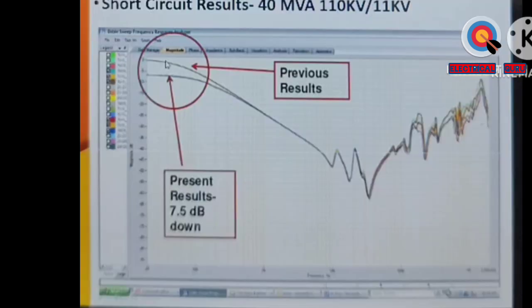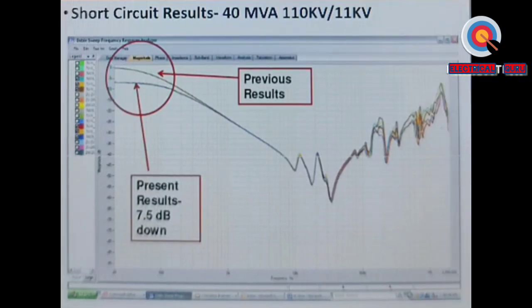See, here we are seeing a typical good short circuit result. Now here you can see the roll-off has changed. And then when we asked the customer if they did any winding resistance measurements on these transformers, they said yes. Just the previous week they had done winding resistance measurements. Now, in winding resistance measurements, we are injecting 100 ampere DC current.